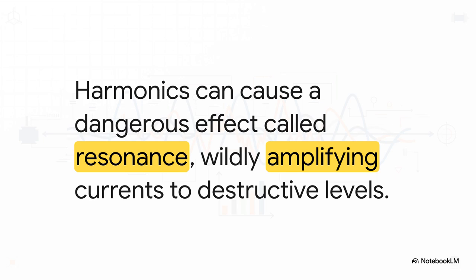And then there's resonance, and this is where things get genuinely scary. Think about pushing someone on a swing: if you time your pushes right, at the right frequency, that swing goes higher and higher. Harmonics can do the exact same thing to an electrical system, creating resonance that can wildly amplify currents to destructive levels.